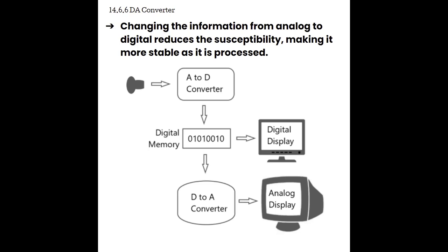typically it would go through amplification in the receiver and all the other processes, but it was still really susceptible to being contaminated by outside electrical interference. So changing the signal from analog to digital reduced the susceptibility, making it really more stable as it was processed through the scan converter. The problem is, though, that if you had an analog display connected to your digital scan converter, the analog display couldn't read the information.